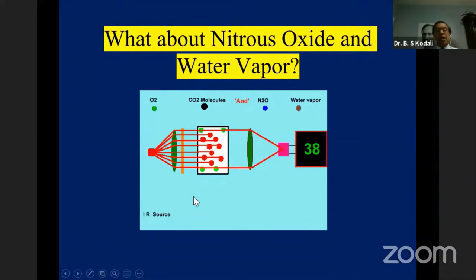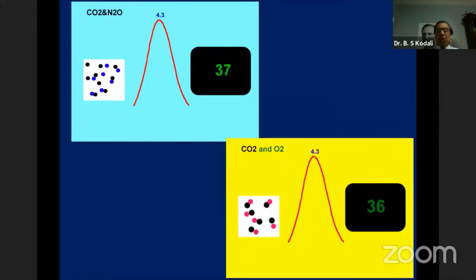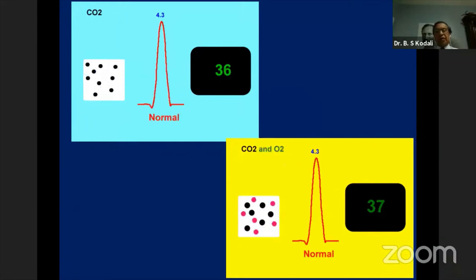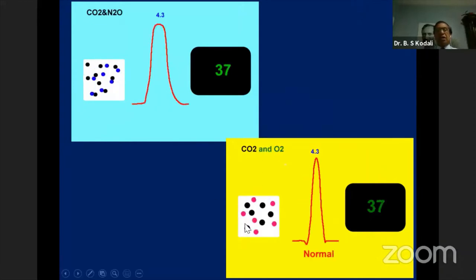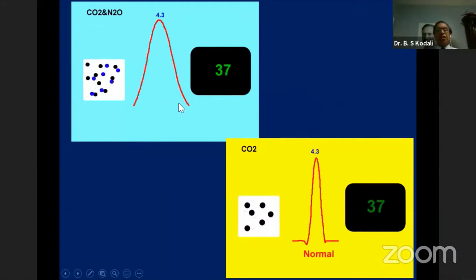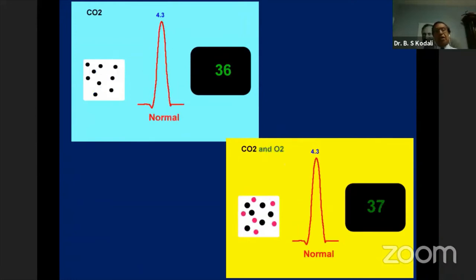Oxygen is not a polyatomic gas, so it does not absorb infrared light. We use paramagnetic technology to measure oxygen since it is a paramagnetic gas. Although oxygen does not interfere with infrared absorption, CO2, nitrous oxide, and oxygen molecules collide with each other, producing interference in the infrared absorption spectra of CO2 — a collision broadening effect — and the monitor also gives correction for this.